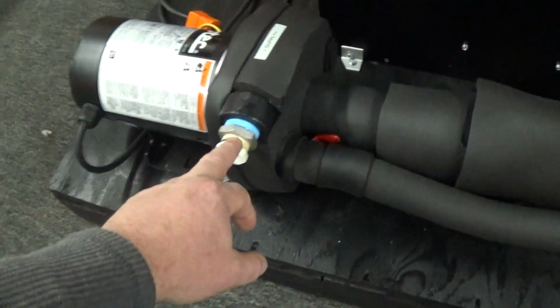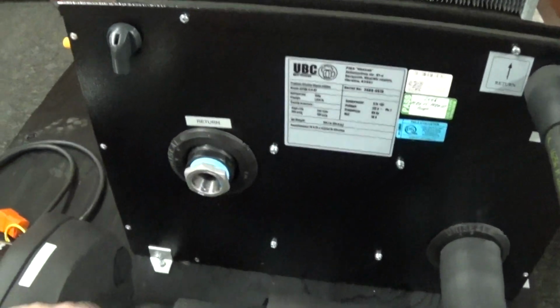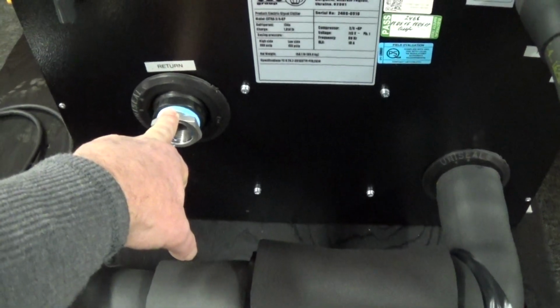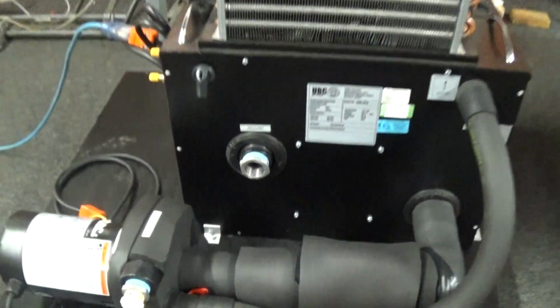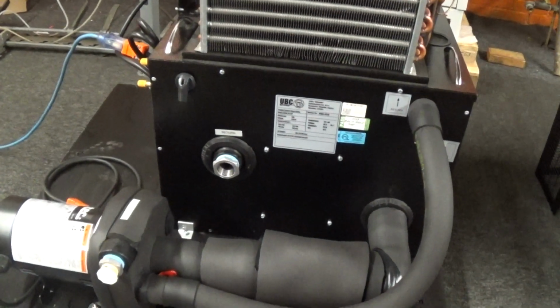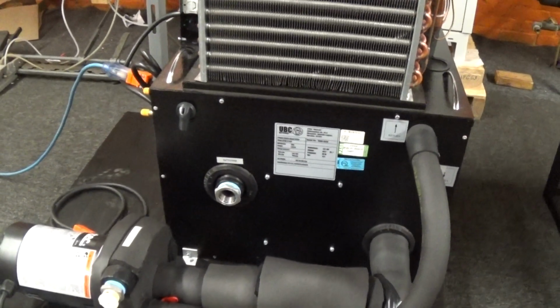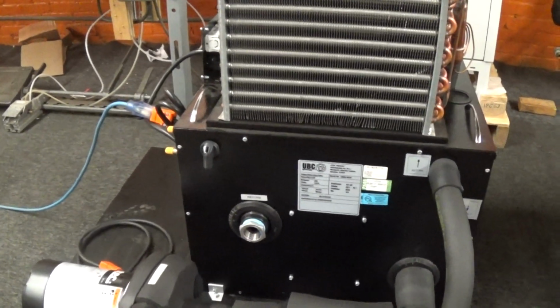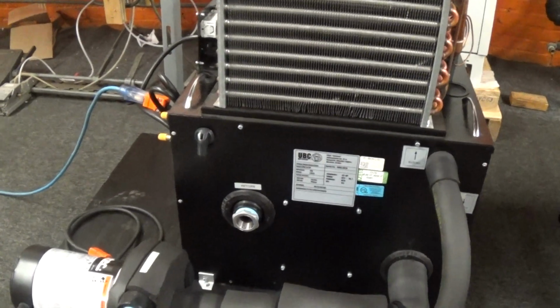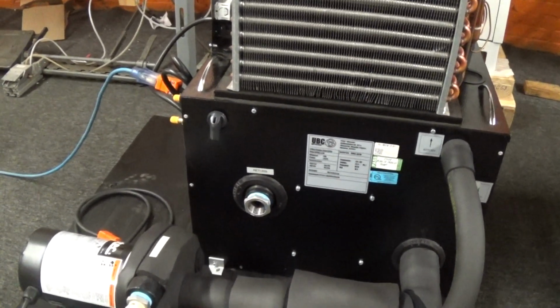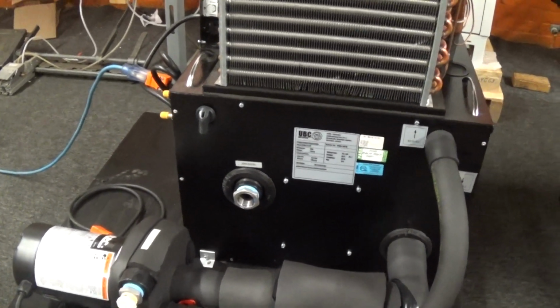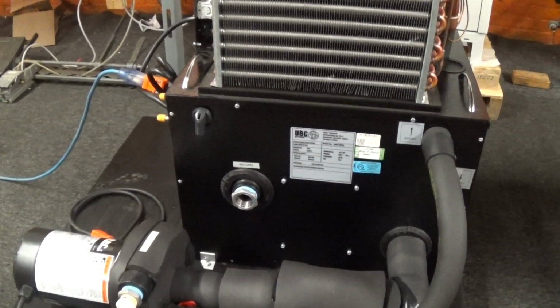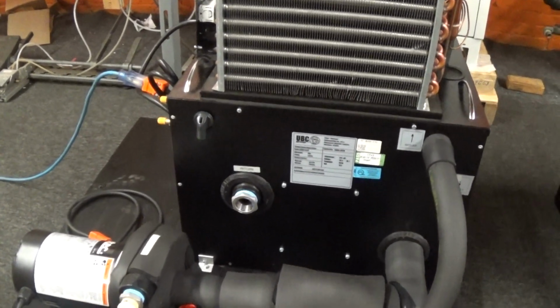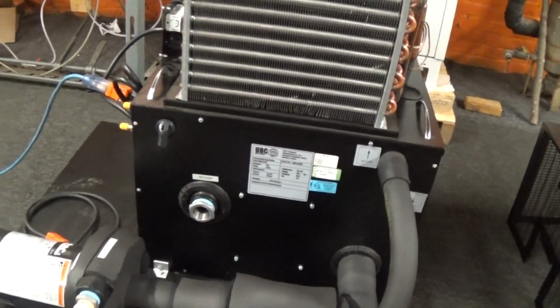So this is your output, 3/4 inch, and this is going to be your return from your Glycol loop. That's going to be 1 inch. You want your return slightly bigger than the supply. We don't require any real PSI or pressure on the return. So for that reason, take advantage of that and use a bigger line size on your return, so the pump doesn't have to work that much harder to overcome that pressure.